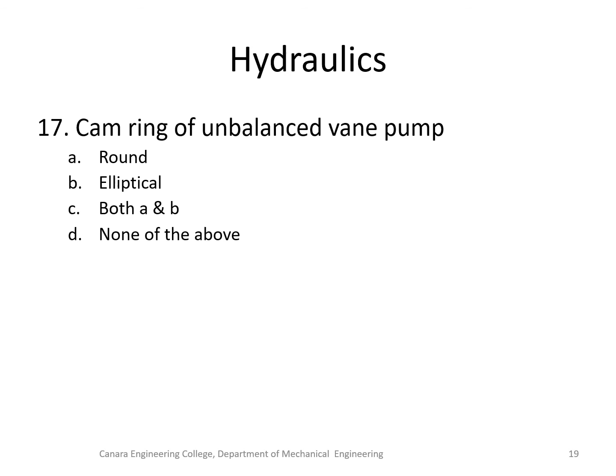The round camming is used in an unbalanced vane pump to adjust eccentricity with the housing, so that variation in flow rate can be achieved, and it is called a variable displacement pump. Elliptical camming is used in a balanced vane pump, with eccentricity with the housing fixed, so that variation in flow rate cannot be achieved, and it is called fixed displacement.